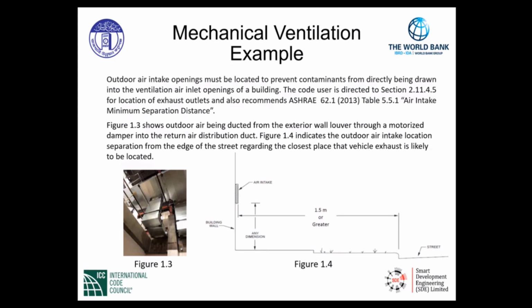contaminants. Figure 1.3 shows an outdoor air intake being ducted from the exterior wall louver through a motorized damper into the return air distribution duct. Adjacent to that, figure 1.4 indicates the outdoor intake location separation from the edge of the street regarding the closest possible point that vehicle exhaust is likely to be located.